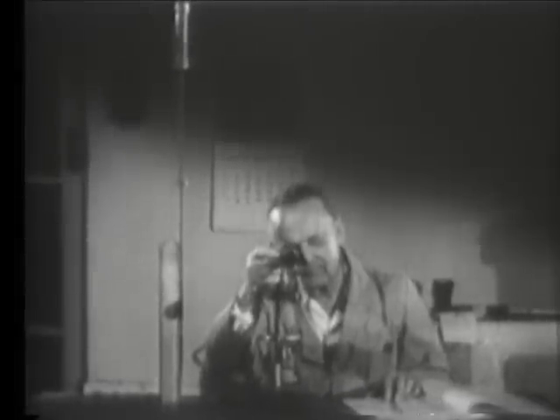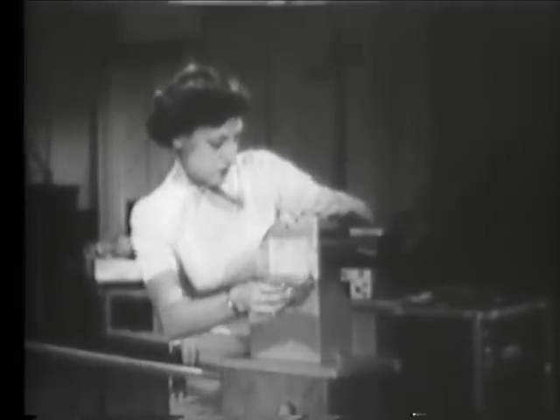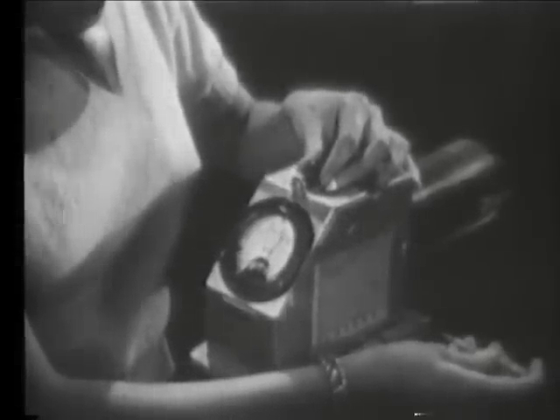This is often done by means of a calibration trolley, which consists of a lead shield in which a radiation source is housed, a movable stand on which the instrument is mounted, and a table with a small telescope. The method of testing and adjusting is simple. The Cutie Pie is placed on the stand. A reading is taken by the operator, and if an adjustment is necessary, it is made by the assistant.